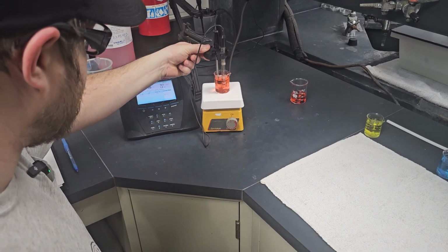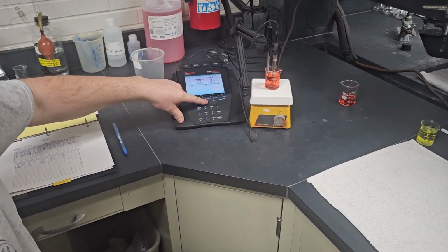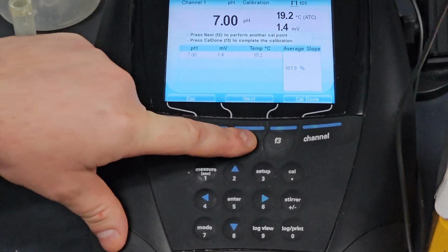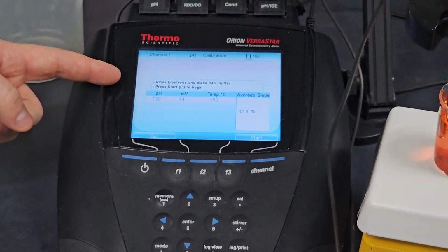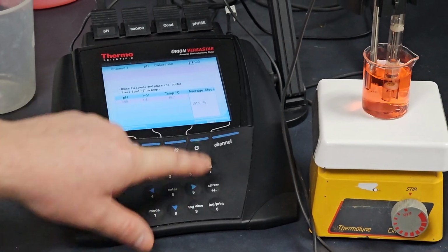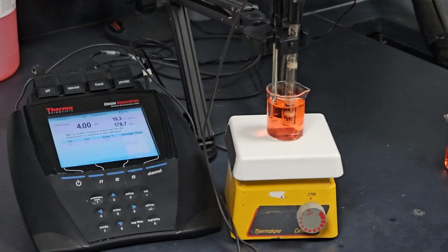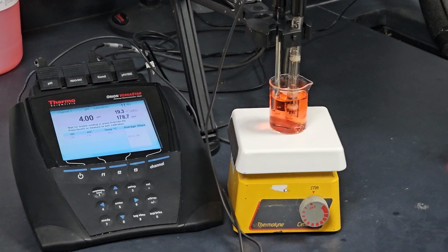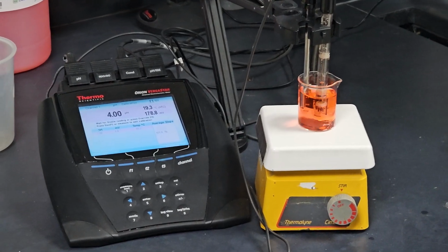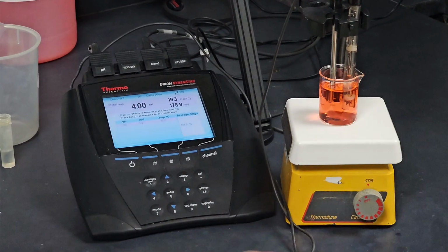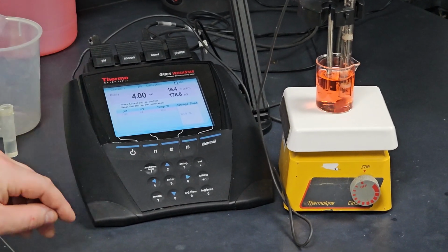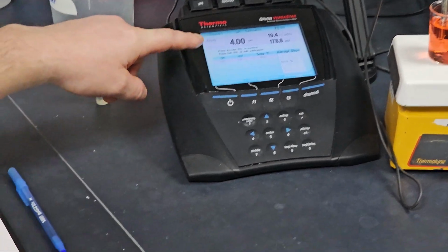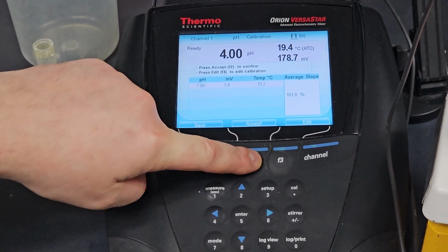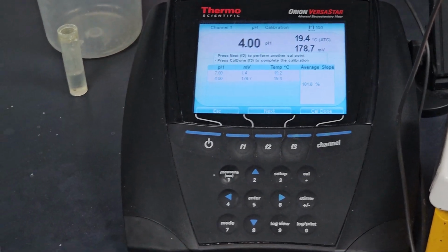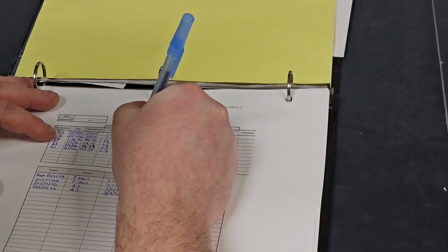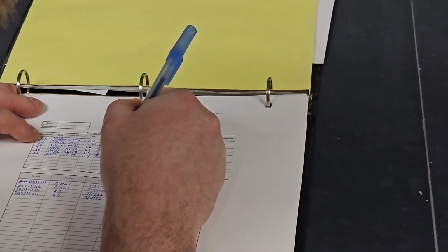And then put the probe in that. And then on the screen we will hit F2 for next. Place into buffer and start to begin. So now we hit F3 to start. Now it is reading our 4 buffer solution. It says ready. It's reading 4, so that's fine. We don't have to adjust at all. We just hit F2 to accept. And we record again the millivolts. 178.7.